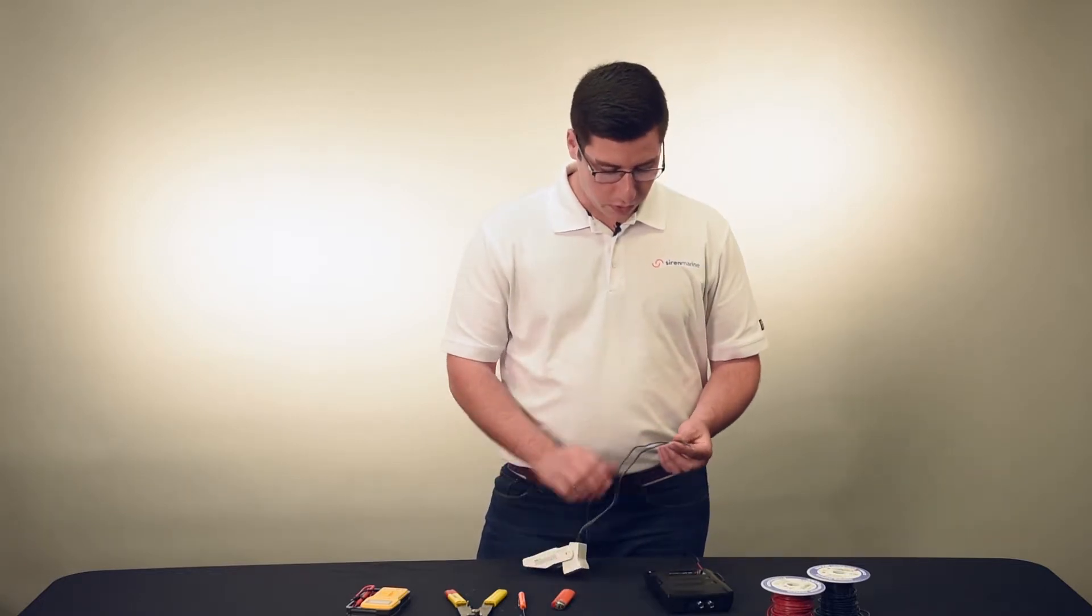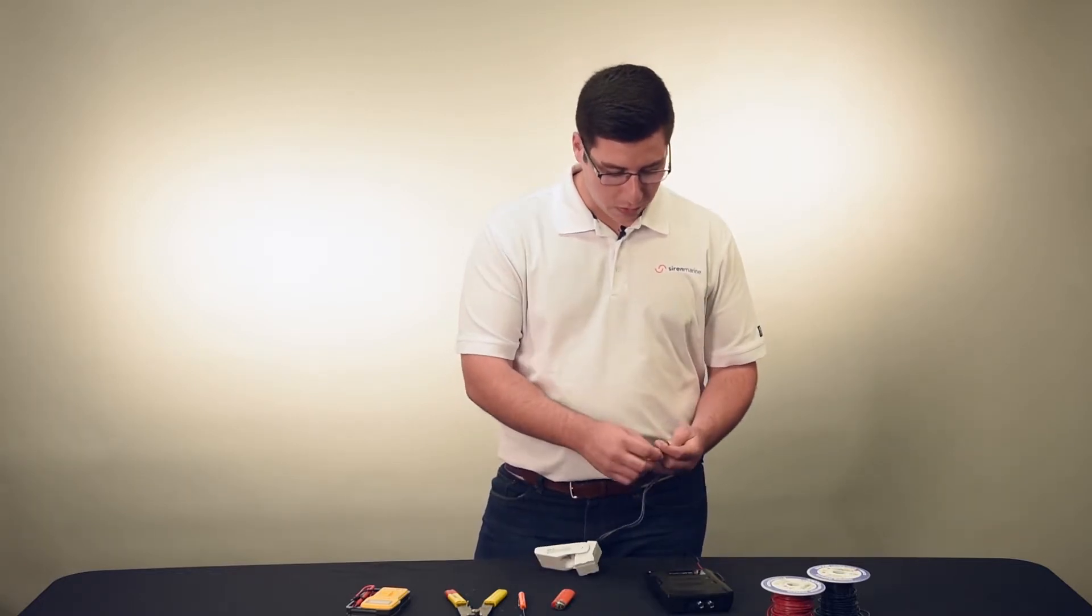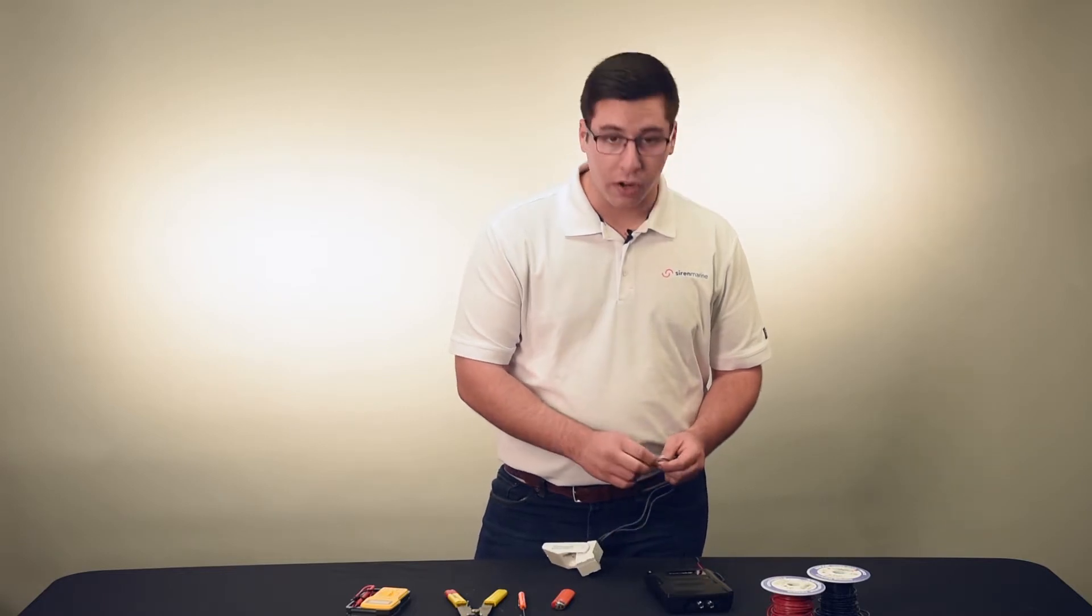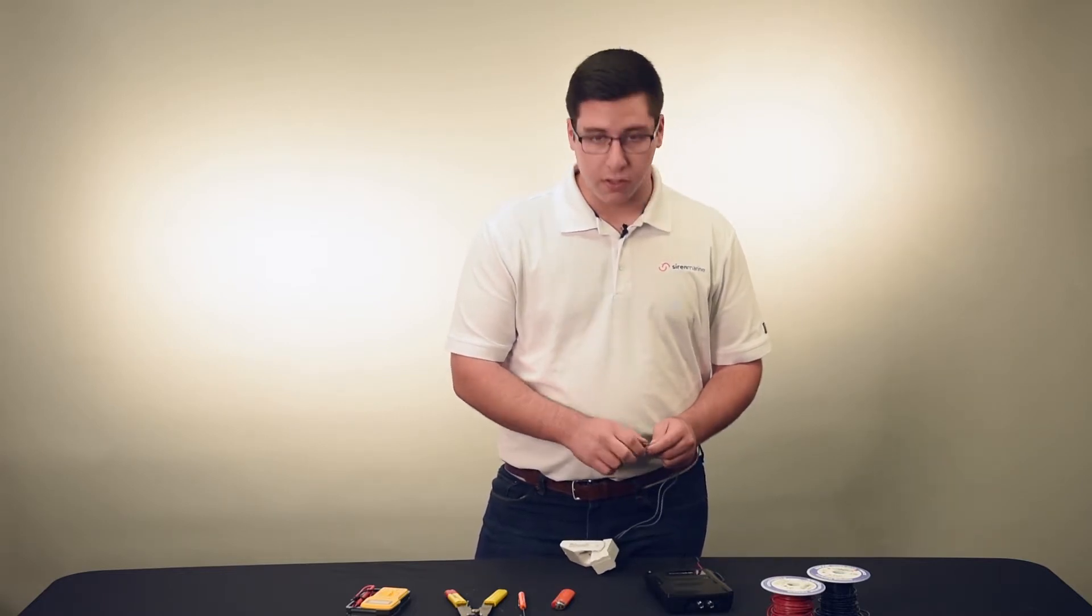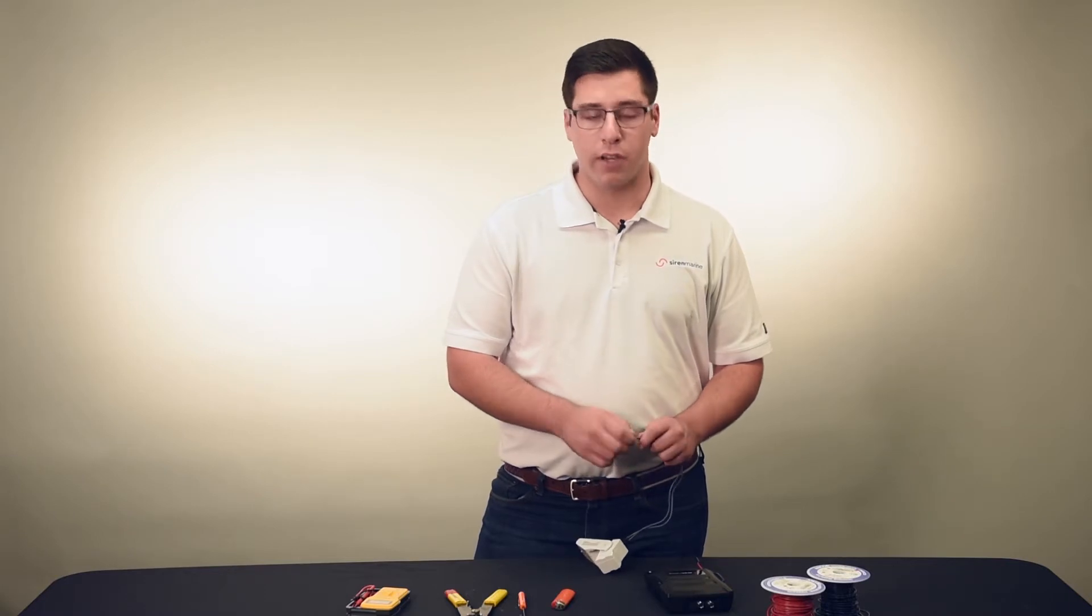Now this rule float switch, again there's no power here. So we're going to be connecting one side to the high water input on the device and the other just looping it into battery ground that the device is already connected to.